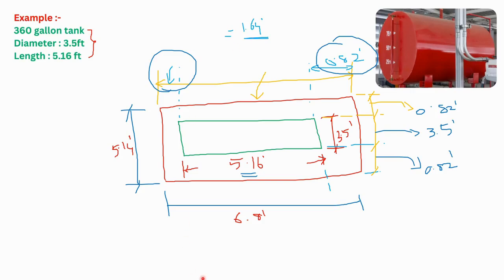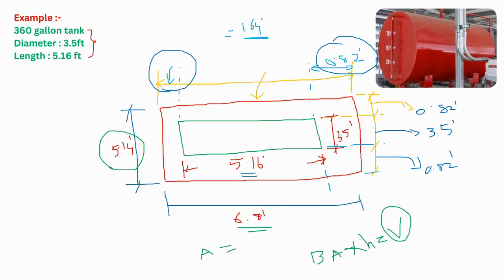Our aim now is to calculate the bund wall area and also the height of this bund wall. We will multiply the bund wall area by height to get the volume. The area of the bund wall will be 6.8 feet multiplied by 5.14 feet, which comes around 34.95 square feet.